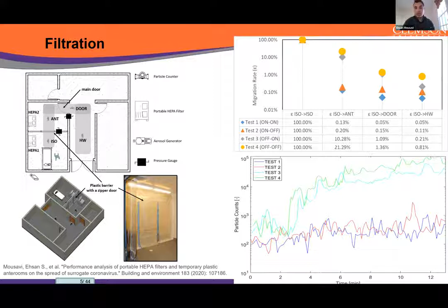I have a trend of particles that are going up, they're accumulating. Now, if I turn off the HEPA filter inside the isolation space, this one, I get a very similar result. So the outcome of that for me was that if you have only one HEPA filter, put it next to your patient. Put it next to the source, and don't put it closer to the door. So that's one outcome that I found.